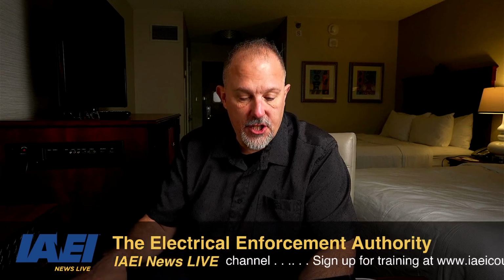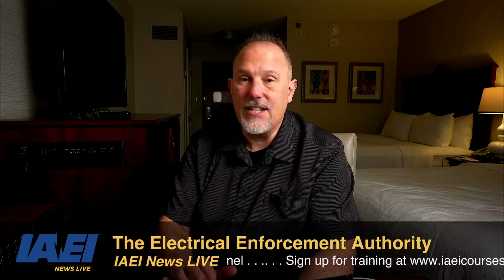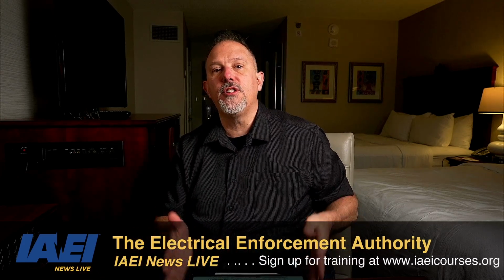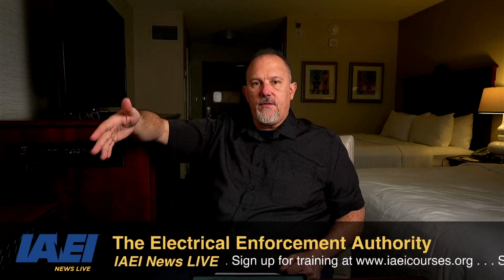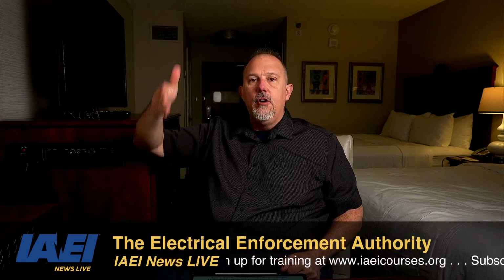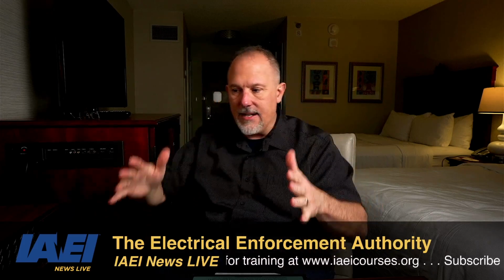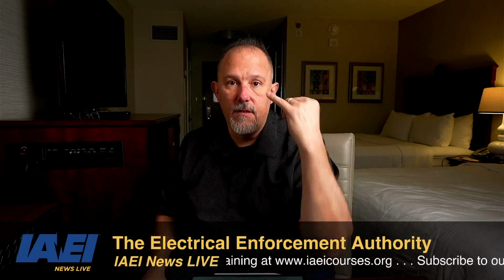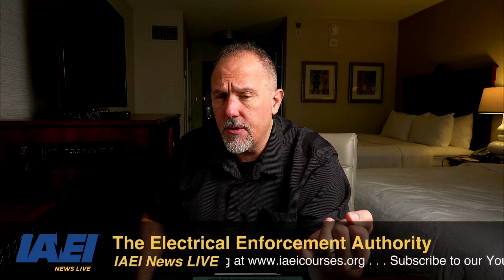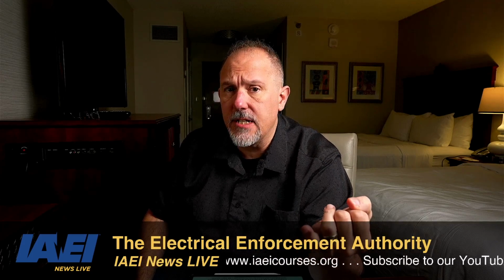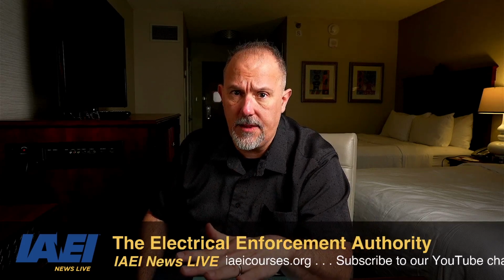You have the emergency shutdown of the prime mover. That's your emergency. So remember what we did on emergency disconnects. We put some requirements for dwelling units for emergency disconnects. And then they said, well, wait a second. What if I have photovoltaics? We didn't have to put an emergency disconnect in on PV because there's the rapid shutdown system that's already there.